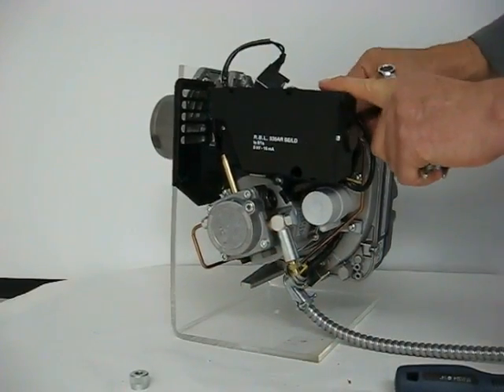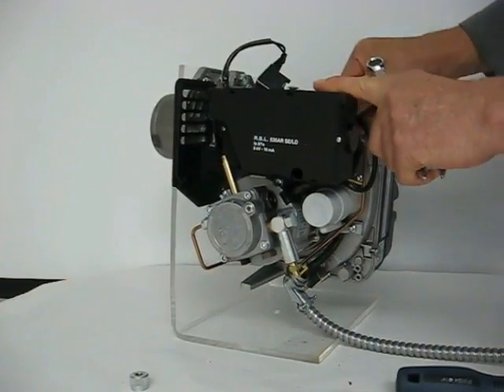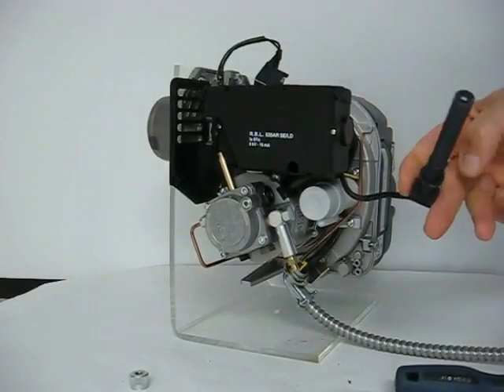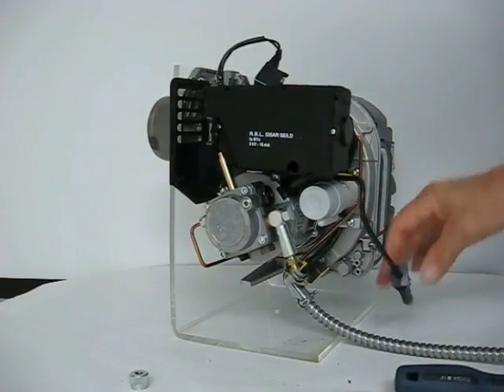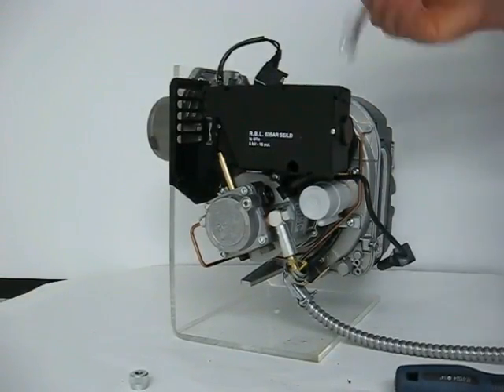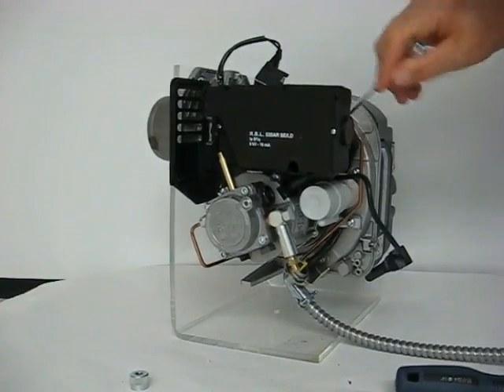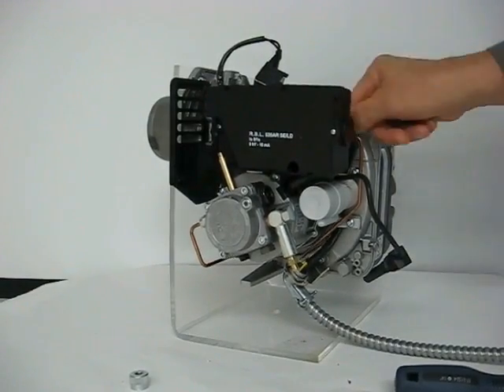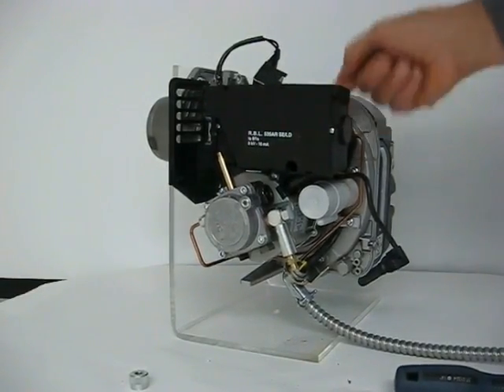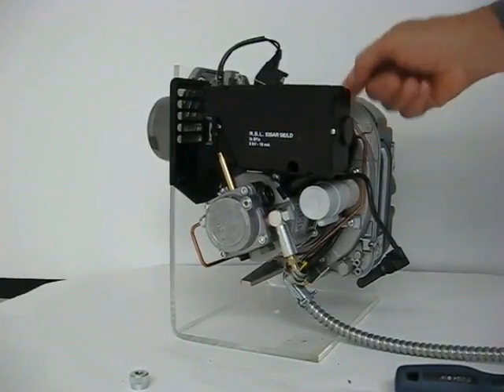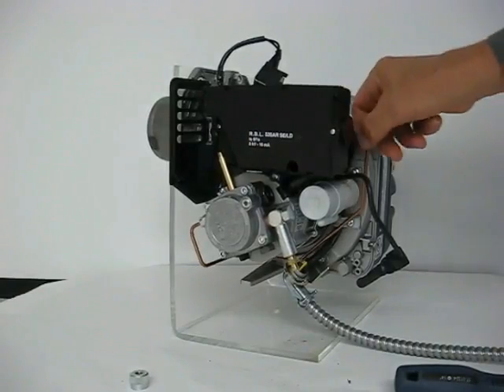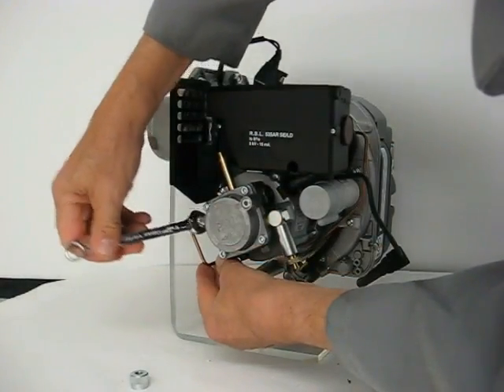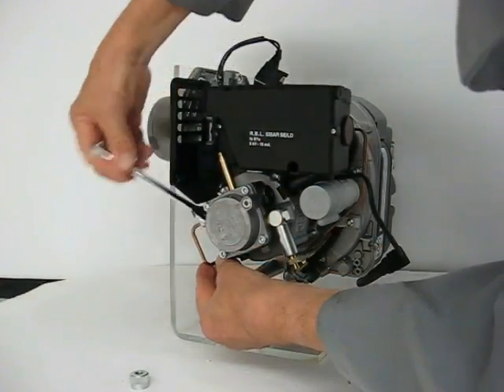First remove the photo cell. It slides off the back of the burner. Using a 12mm wrench, disconnect the connection on the back of the nozzle holder. Disconnect the nozzle line from the pump.